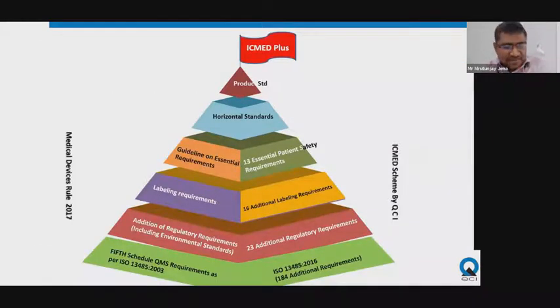This is what I explained in the previous slide, and this is a graphical presentation. One side is the Medical Device Rules 2017. These are the components: the fifth schedule, which is the QMS requirements as per the old 2003 version of 13485. Whereas the ICMED scheme, the latest version, issue number 2, 2019, has been revised to ISO 13485:2016, with some additional requirements. Second are additional regulatory requirements, including environmental standards as per the MDR rules. Similarly, in our revised ICMED version, we have added 23 additional regulatory requirements.